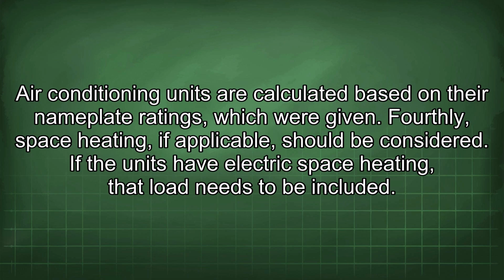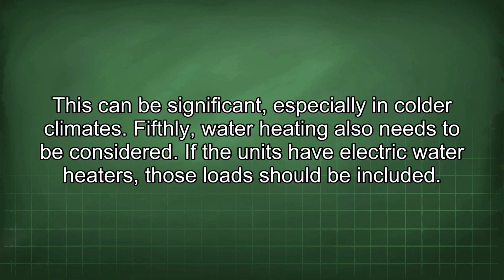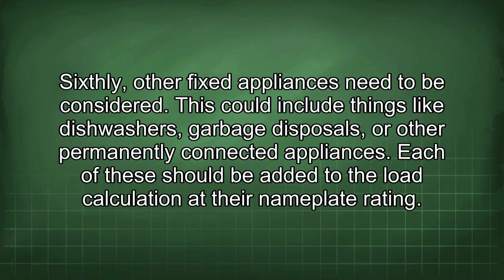Fourthly, space heating, if applicable, should be considered. If the units have electric space heating, that load needs to be included. This can be significant, especially in colder climates. Fifthly, water heating also needs to be considered. If the units have electric water heaters, those loads should be included. Sixthly, other fixed appliances need to be considered. This could include things like dishwashers, garbage disposals, or other permanently connected appliances. Each of these should be added to the load calculation at the nameplate rating.